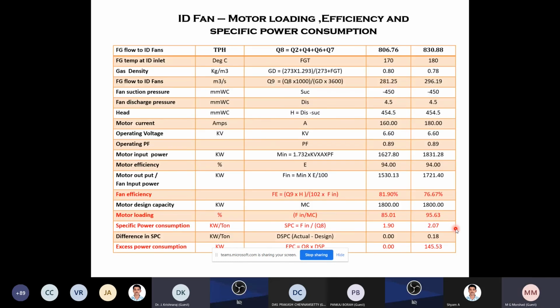Now likewise, what we have done: motor loading, efficiency, specific power consumption, all the data we have collected. After that, fan efficiency: you see the design is 81% efficiency, but we are seeing 76%. Okay, motor loading: the designer has given 85, but here it is 95. See how much overloaded the motor is. Specific power consumption: design 1.9, here 2.07. So the excess power consumption is 145 kilowatt. So 145 kilowatt is the excess power, you can say the auxiliary power consumption. Automatically your auxiliary power consumption will increase and your net heat rate will also increase.